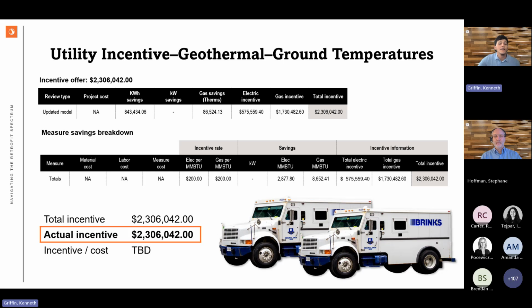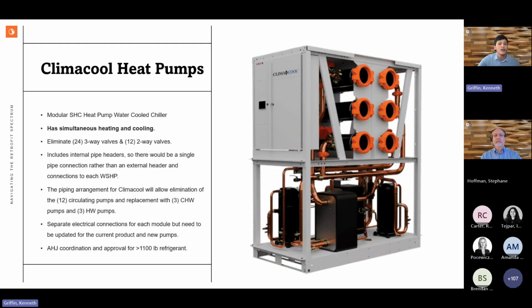The next part of this was we had a change of our heat pump system. Based on the cost of our previous heat pump system and some interest in a slightly different system, we looked at Climacool's modular SHC heat pump water-cooled chiller. The real benefit here was simultaneous heating and cooling that our previous heat pump didn't have. It allowed us to eliminate valves and simultaneously heat and cool.